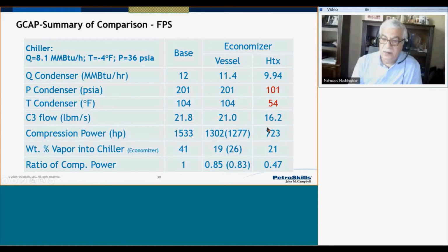But this may not always be available, the cooled process gas. So if no cooled process gas is available, then instead of this, you go to the economizer with extra capex and opex. But you do a lot of saving on the compressor side, both capex and opex as well. Percent of vapor into the chiller: 41% for the simple refrigeration system, 19% with the economizer. I put 26 in the parentheses for the economizer because in the mechanical refrigeration system with the flash tank economizer, we had two JT valves. One of them for the economizer, one of them upstream of the chiller.